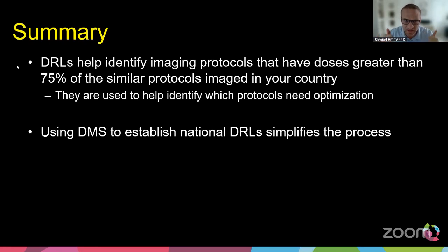We should ask ourselves, is the image quality appropriate? And if it's appropriate, we can be okay with that. If not, we can maybe bring it down to the 50th percentile. We should never, once again, use these DRLs as a punitive quantity to say, oh, this patient exam got too high a dose. That's not the case. It's not applied specifically to an individual, but more specifically to an exam type or a machine.